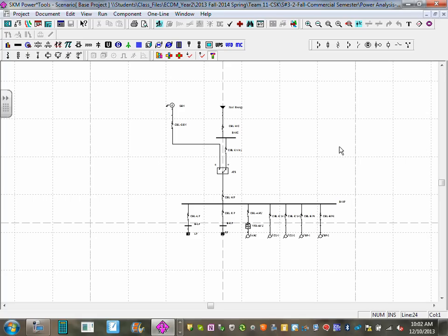Any comments, guys? Any questions? Garbage in, garbage out. You guys know how to use the software now to interpret the information. It will give you the available short circuit in every panel. That's what you need to know. And it will give you the arc flash. You can put a label. Can you guys see the arc flash label there? Put a label for your panels. But to do the arc flash label, we need to put the overcurrent protection device in yet. So we'll do that tomorrow. We'll put the overcurrent protection device and do coordination. Any comments, guys? Any questions?